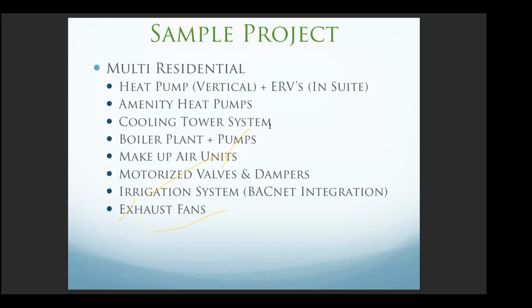Similar thing with the cooling tower system. Sometimes the manufacturer may supply a control system, or a controller for the cooling tower, depending on how the spec is written. And if that is the case, then the controls contractor would go and wire up all the points to that controller and install that controller. And if that is not the case, then we would still wire up the points, but now in this scenario, we will provide a controller at the same time.